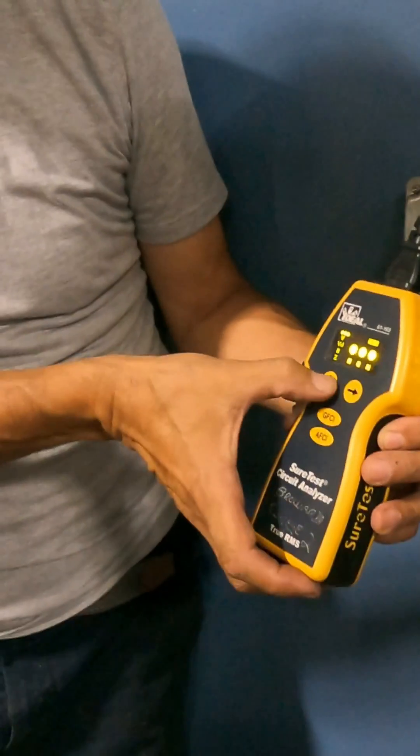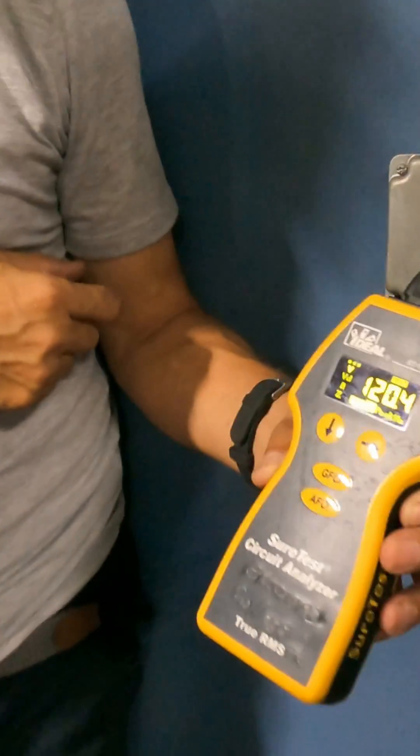Look at this. I am going to connect the SureTest. It says that the hot, neutral, and ground are properly wired in this outlet - you see they are solid: hot, neutral, and ground. Okay, I am going to check voltage. 120 volts 0.4, that's good.